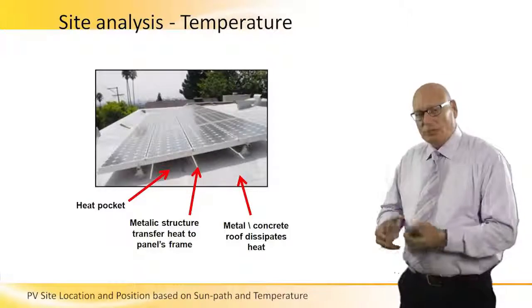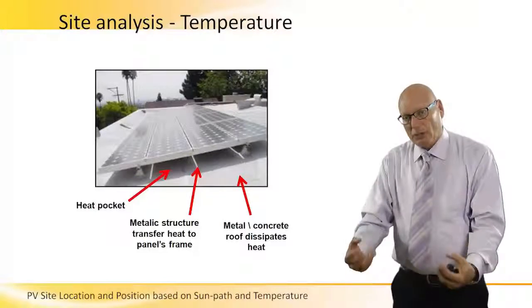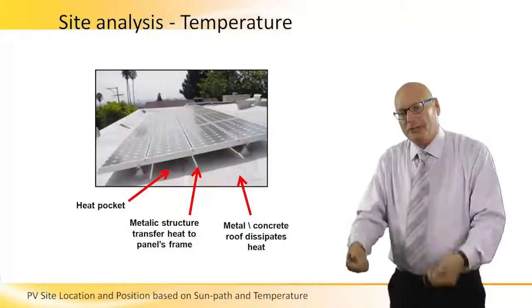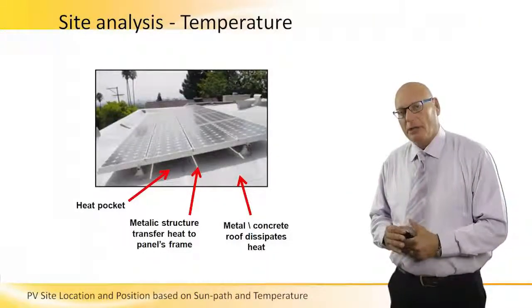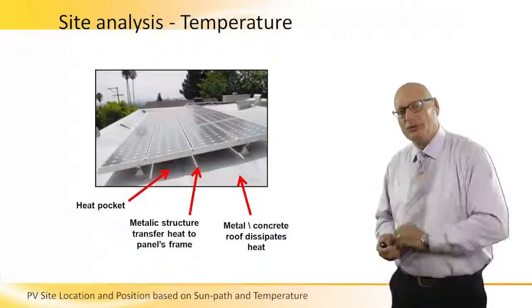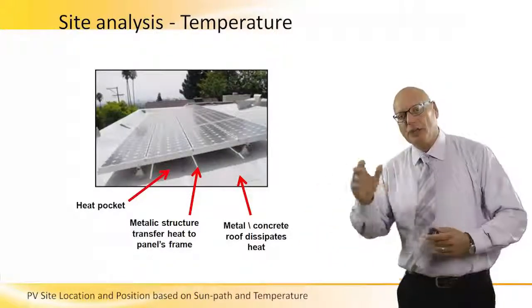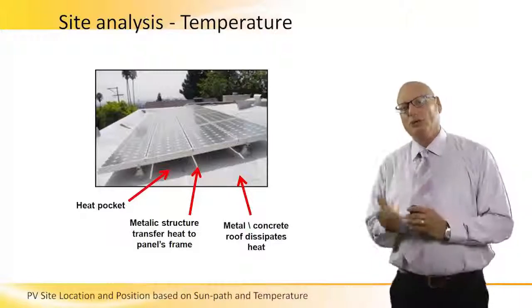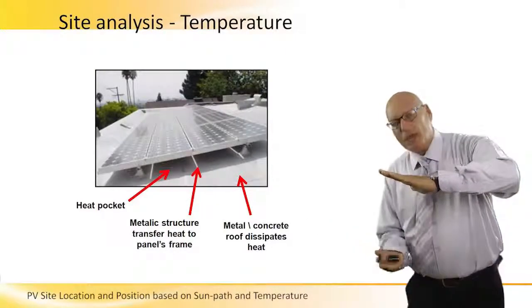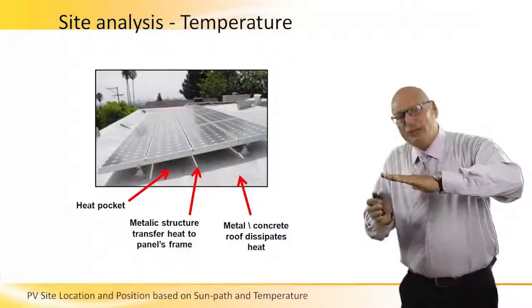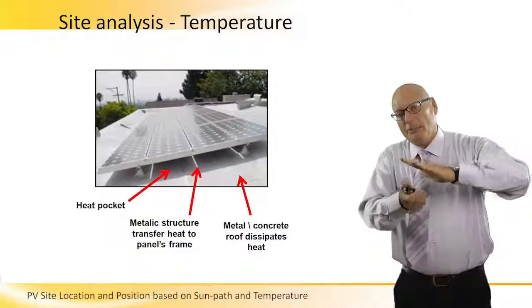Another thing is the metallic structure. We can see in the center the metallic profiles and this structure, which is mechanically connected to the roof. Because it's metallic — and usually it's aluminum — aluminum by its nature is a very good heat conductor. So not only do we create a heat pocket, but the heat will be transferred through the structure to the panels. The metallic roof will transfer its heat to the metallic structure, which will heat up the backside of the panels.